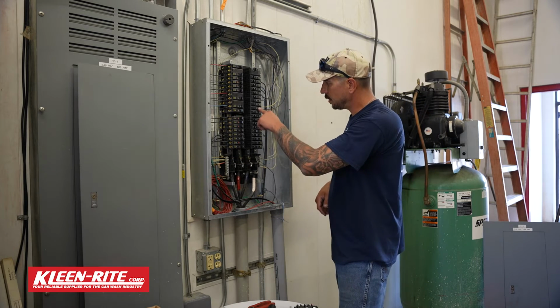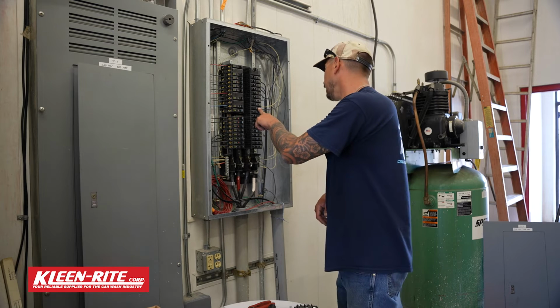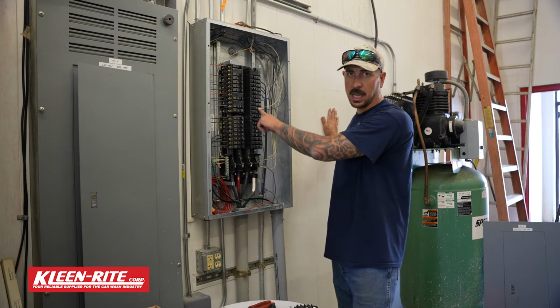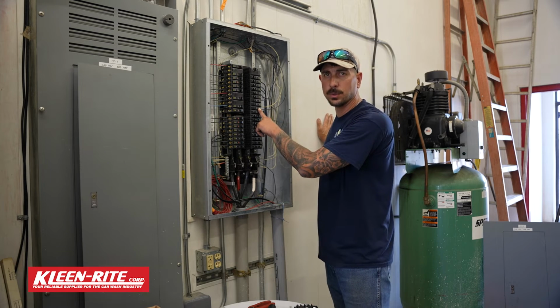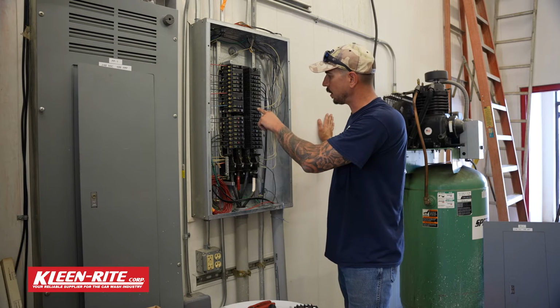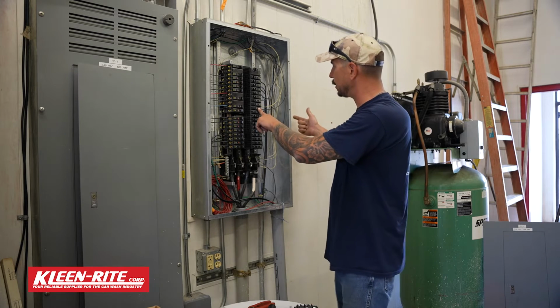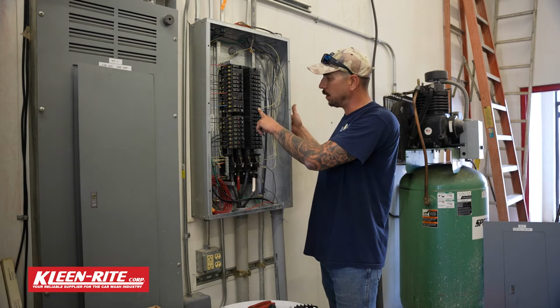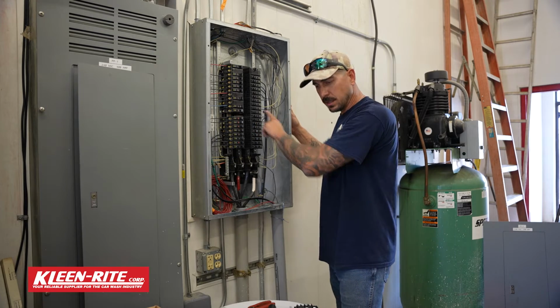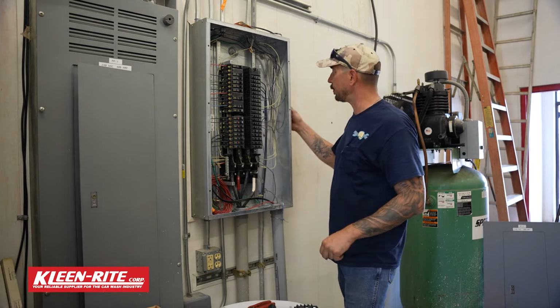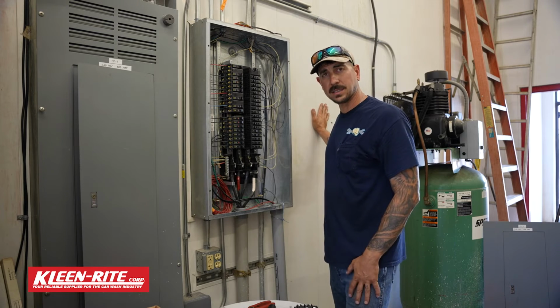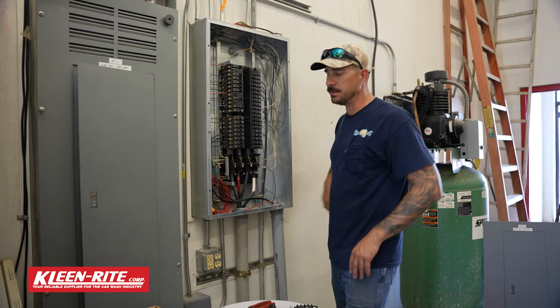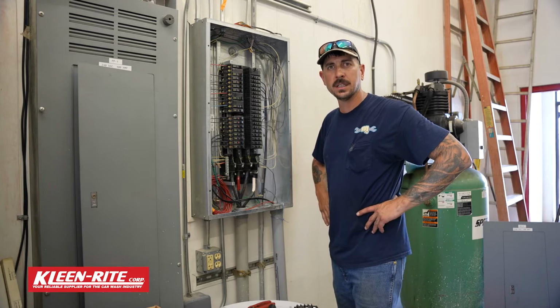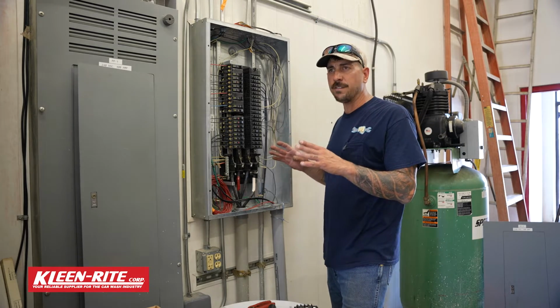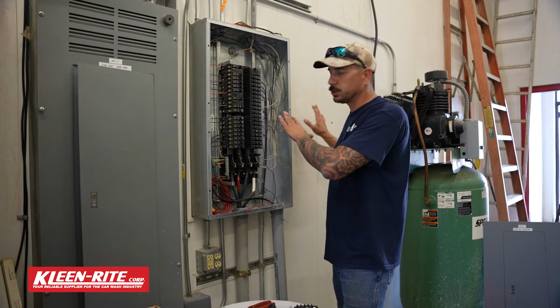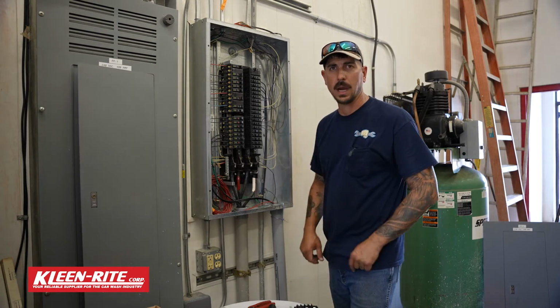I have this 30 amp breaker right here that is almost directly in line with where I need to mount my box to add in my transformer. So I'm going to pick this breaker, and what I'm going to need to do is pop a hole in the side of this box so that we can run a conduit from this box over to the box that our transformer is going to be mounted in. So let's get all that stuff fit up here quick, and then we'll drill some holes, and then we're going to show you how to wire this.